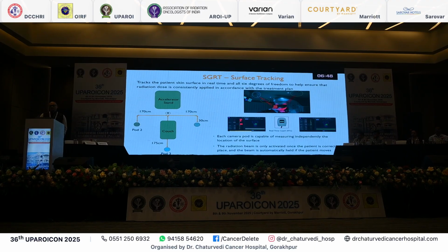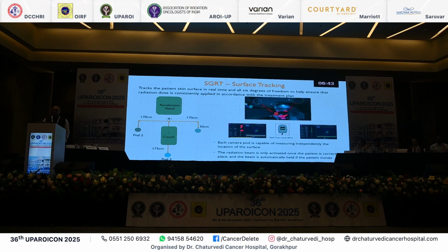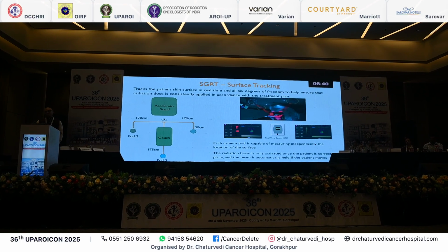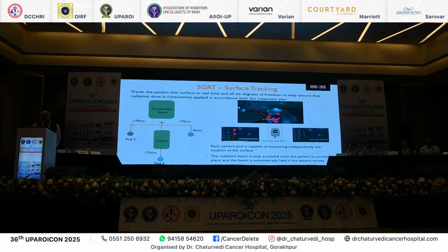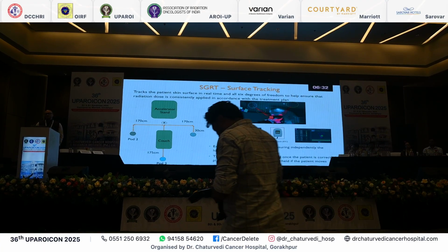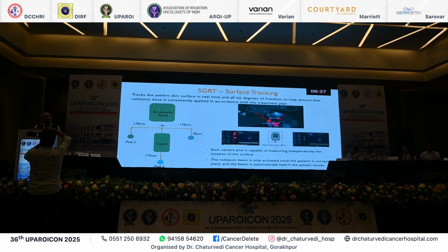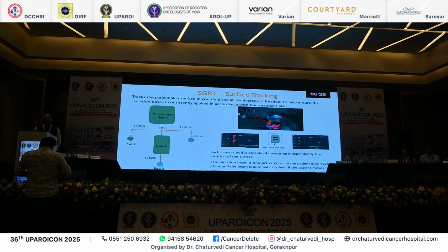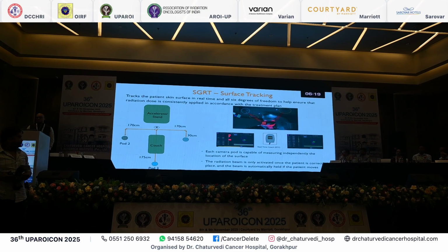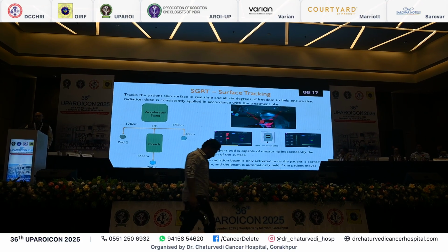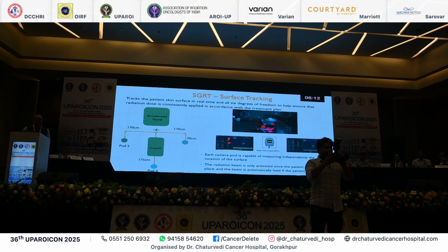Then coming to another aspect of motion management, that is optical tracking. This is one of the current hot topics of motion management and has built up a whole industry, which runs into millions and millions of dollars. SGRT is surface guided radiotherapy, whereby surface tracking of the tumor volumes is done using 3 cameras positioned in the treatment room, and each camera pod is capable of independently measuring the location of the surface. The radiation beam is only activated once the patient is correctly in place, and the beam is automatically held if the patient moves.